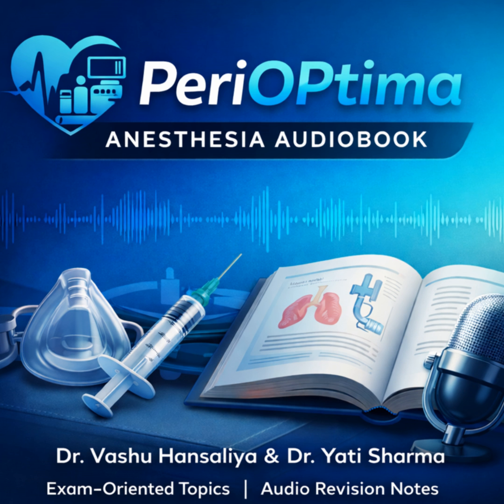What about the pumping effect? I've heard that term. Yes, that's another important safety consideration. This happens during positive pressure ventilation. When the ventilator pushes a breath in, back pressure can travel up the circuit and into the vaporizer.